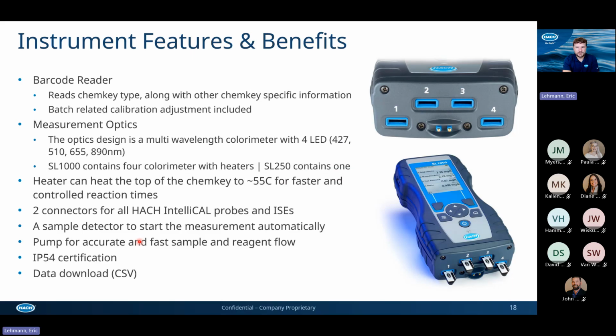So let's talk about the instrument itself. As I mentioned, it does have an internal barcode reader. So it's going to read the chem key itself. It's going to determine what type of sample or what parameter you want to measure. So it's going to pull up the exact wavelength, because it has multiple wavelengths built in. It's going to pull up the wavelength. It's going to pull up the parameter. It's going to read that sample blank, and then it's going to draw that sample in.